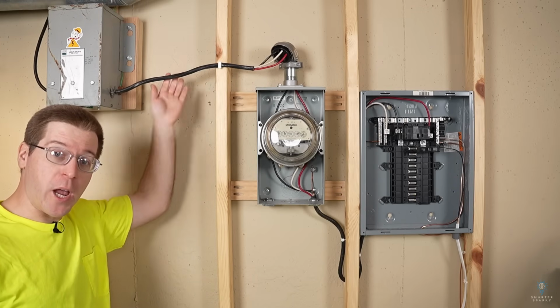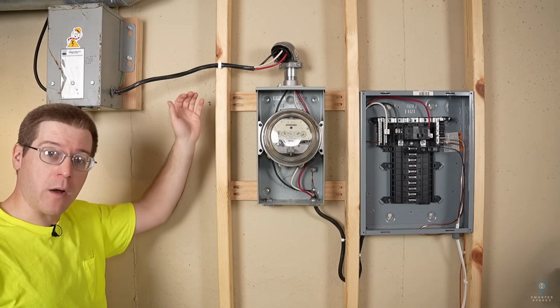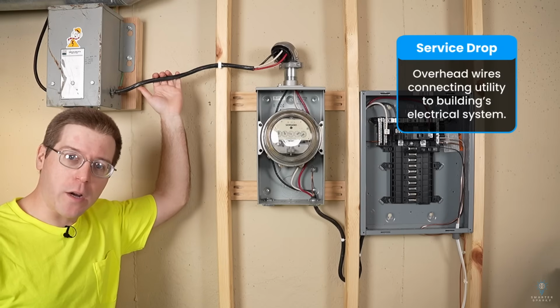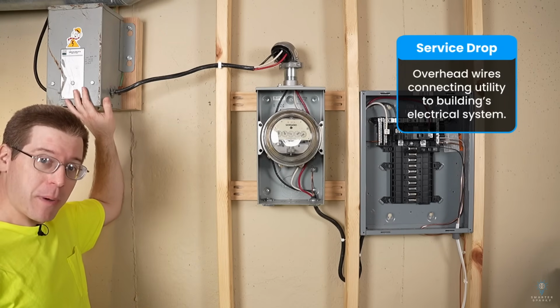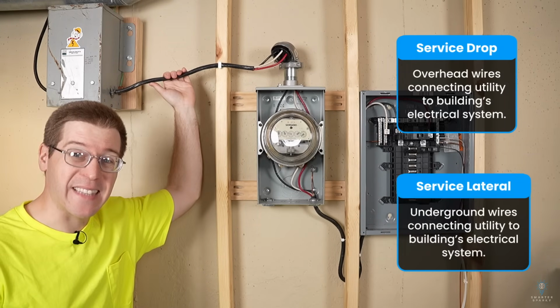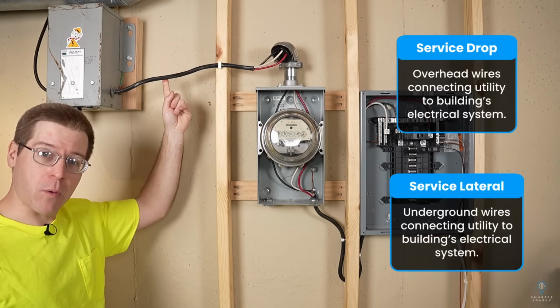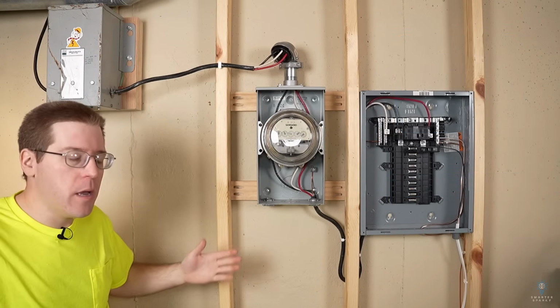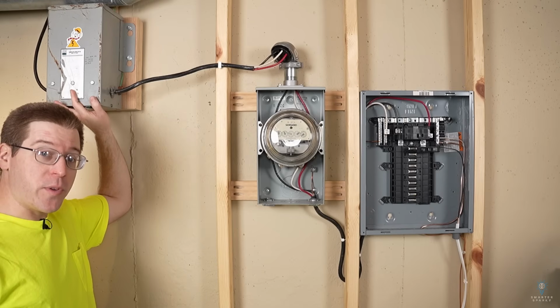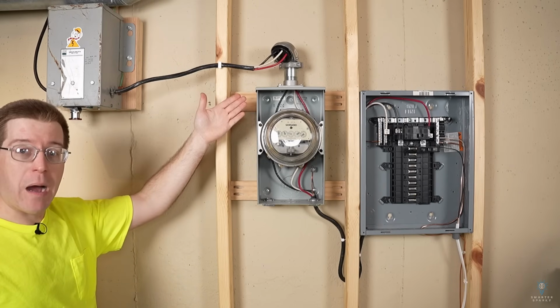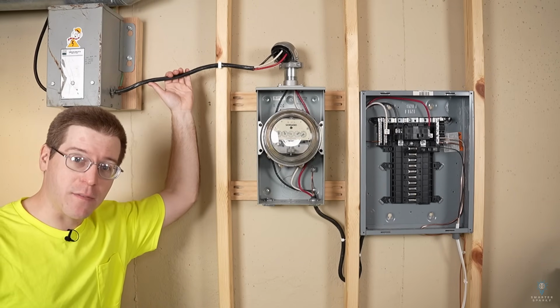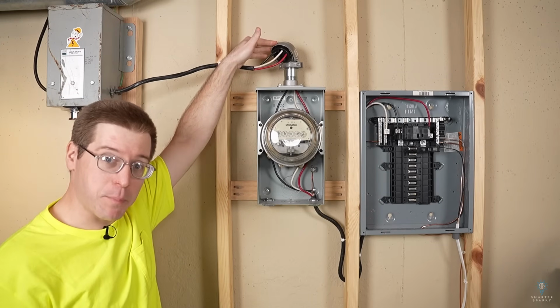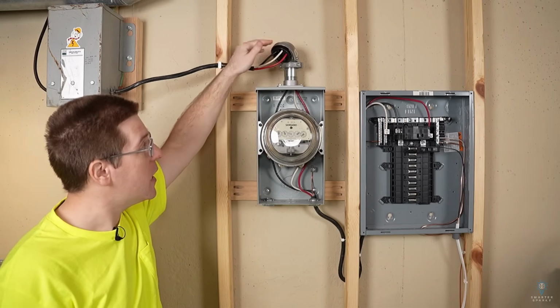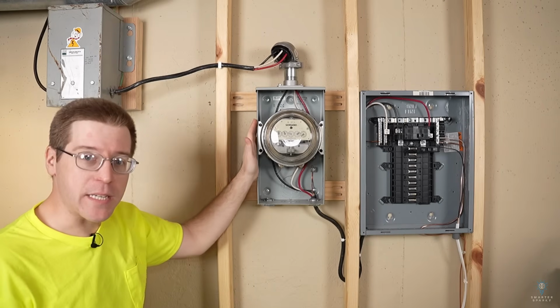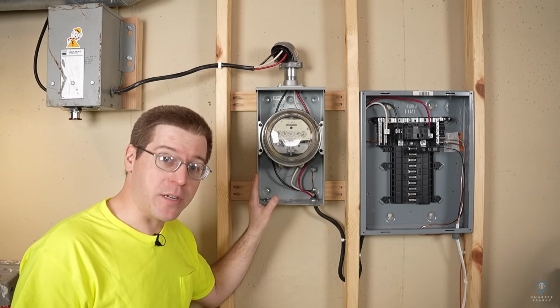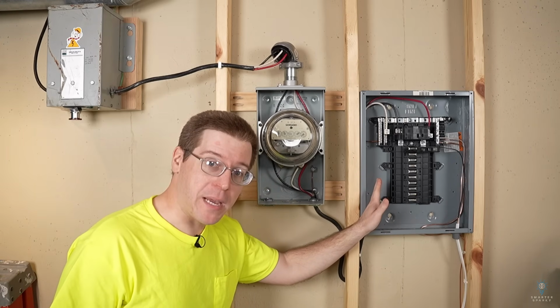This wire going overhead from the utility transformer to your house would be called the service drop. If this wire were underground from a pad-mounted transformer, it would be called a service lateral. Service drop is an overhead wire, service lateral is an underground wire. Otherwise, they do the same thing. So from our utility transformer overhead to our service, this is called the service drop. Once it reaches the mast poking up out of the soffit at your house, it goes down through the soffit and it goes into your meter socket. Then out of the meter socket, it goes directly into our main electrical panel.